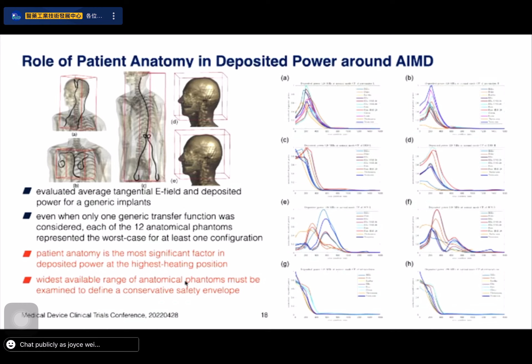So the takeaway from this is that in order to define your safety envelope of what you can experience during an MRI, you need the widest possible range of anatomical phantoms. And that's why we keep expanding those. And then the other part of the tool is the IM Analytics. IM Analytics is a numerical solver. Basically, once you have a field inside the body along the lead that your device is on, and you have a model of your implant, which is how the device will respond to that lead, basically you just take those 2 curves and multiply them and integrate, and you're done. It's actually something you can do in Excel or by hand.